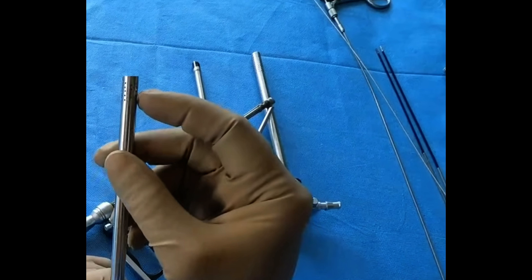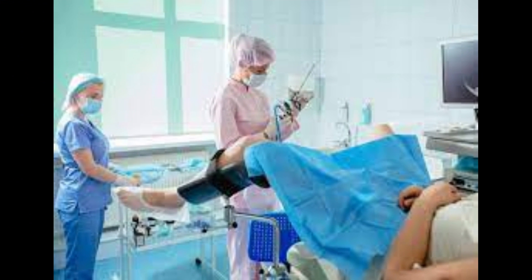Based on function: Diagnostic hysteroscope — used primarily for examining the uterus to identify abnormalities. It has a smaller diameter and is often performed without anesthesia. Operative hysteroscope — equipped with additional instruments such as scissors, electrocautery, or graspers to perform surgical procedures such as removing fibroids, polyps, or adhesions.